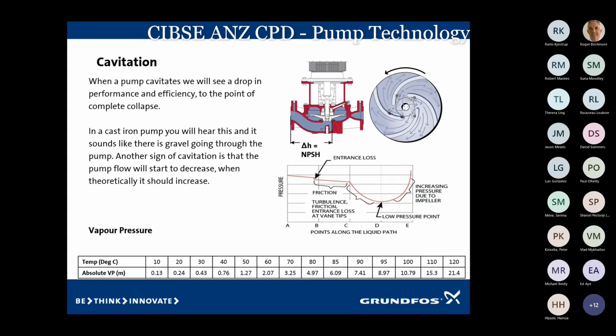So looking at that little chart at the bottom here, you can follow it down. At A, we've got pressure. At B, we've got some friction loss. We're losing some pressure. At C, we're now losing more pressure due to the pipe work and what have you. As we get to D, all of a sudden, our atmospheric pressure is unable to overcome the net positive suction head required for the pump. And at that point it starts to vaporize, and that's cavitation.